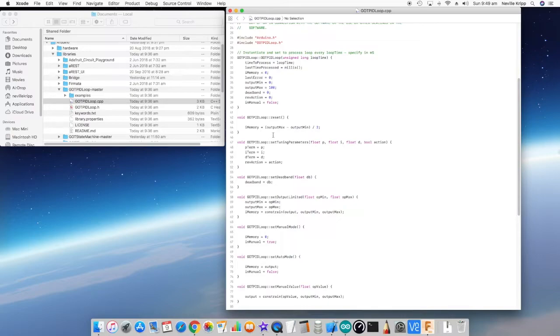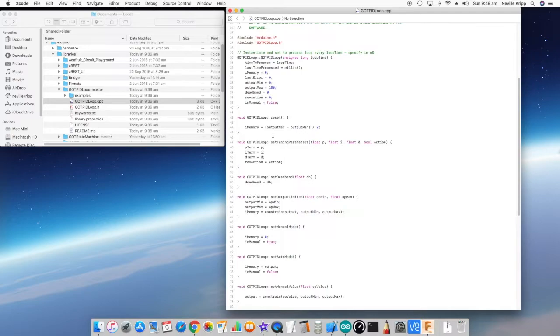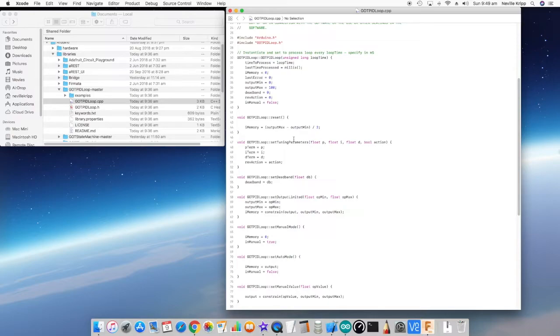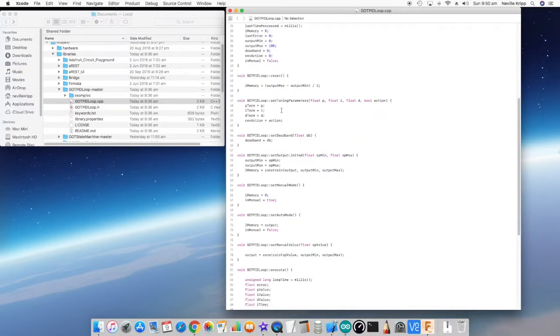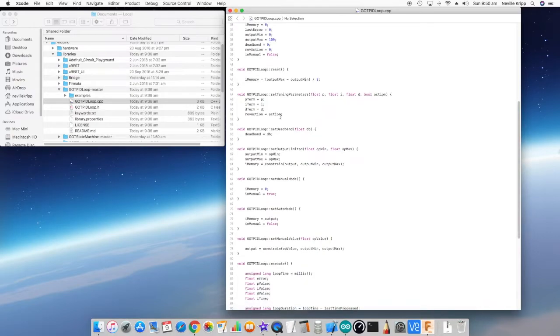The next function we come to is the reset. The reset is used after there's been a change in the control scheme. We can actually reset the integral memory component. We always call that after we set the output limits so that it will set the i memory right in the middle of the actual limits. That way the control act can have the maximum deviation below and above that midpoint.